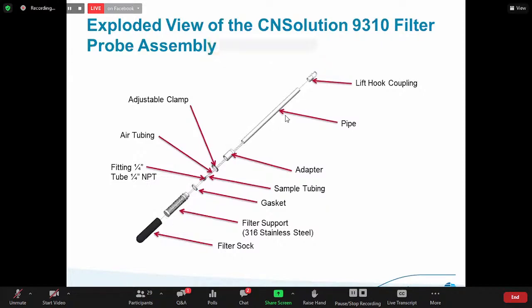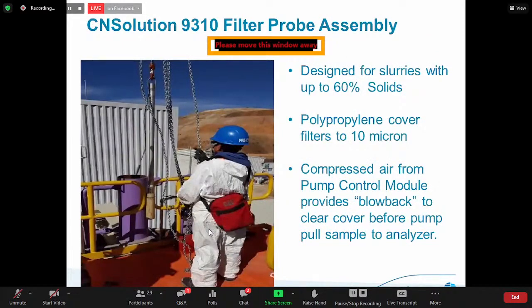But this is supported by this long pipe here and this lifting hook. So what happens is you pull this out of the slurry, service this end of it, and drop it back down again. And here you see that. This is a technician raising or lowering the sample probe. Here's the hook that holds it here. This is the pipe that supports it. There is the filter element at the end of it, covering the collection device at this end of it.